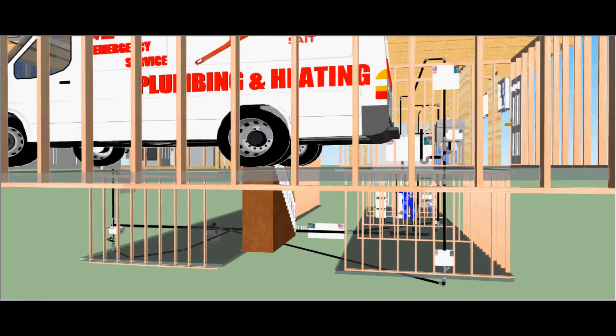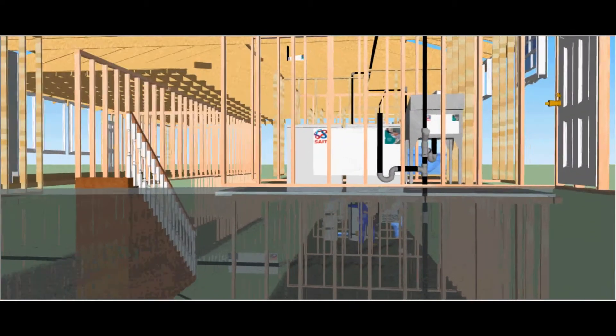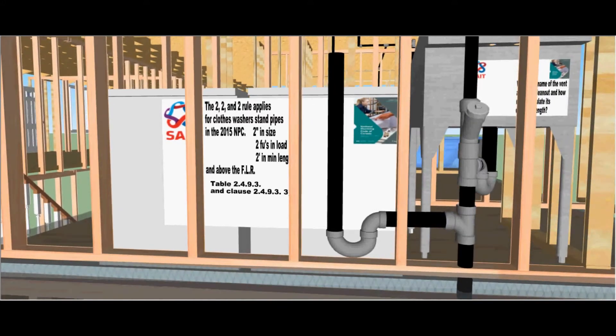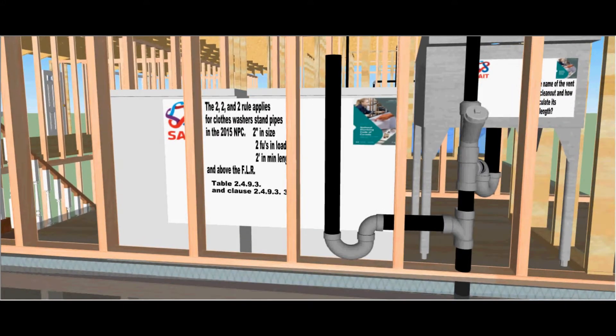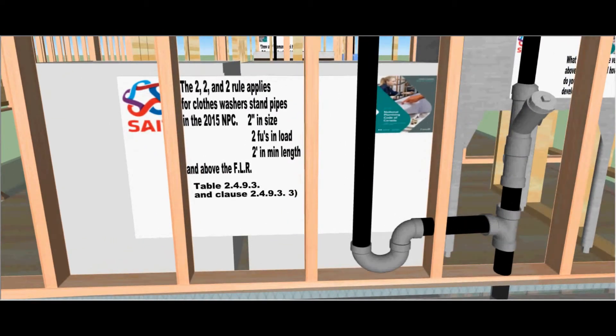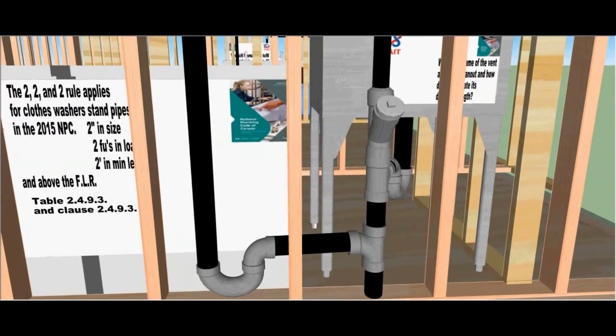Now let's take a look at our laundry setup or clothes washer machine. The 2-2-2 rule applies for clothes washer standpipes in the 15 code: two inches in size, two fixture units of load, two foot minimum length and above the flood level rim. This is found in table 2493 and clause 2493 subsection 3.